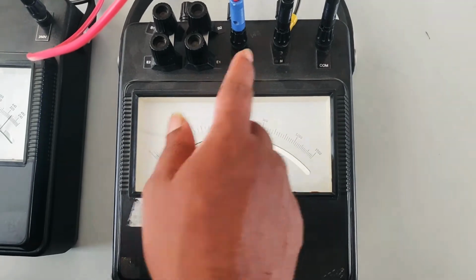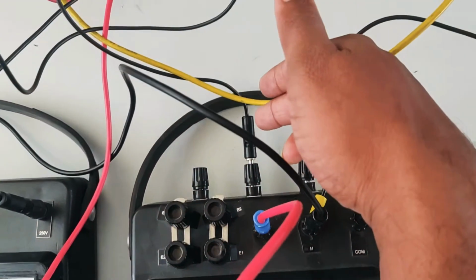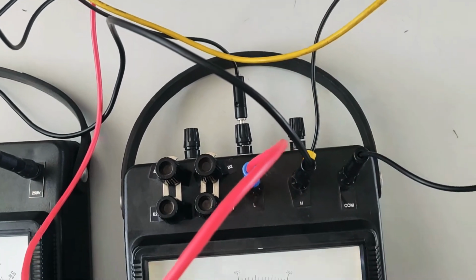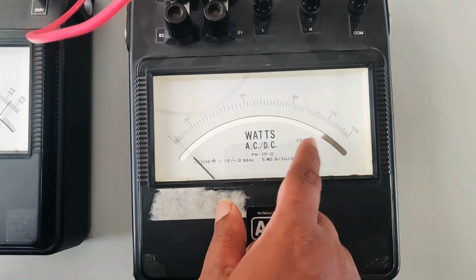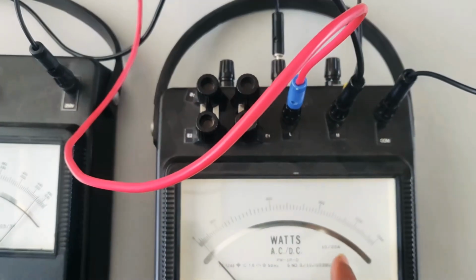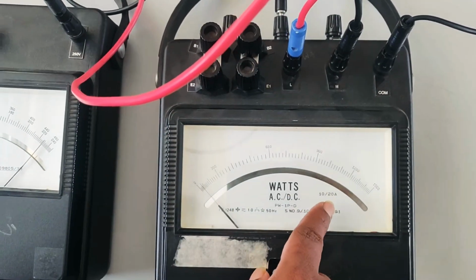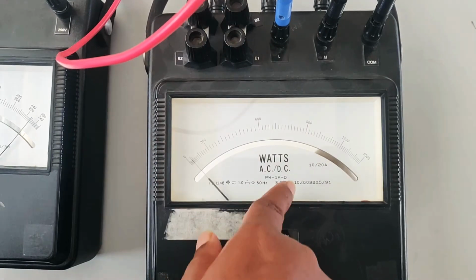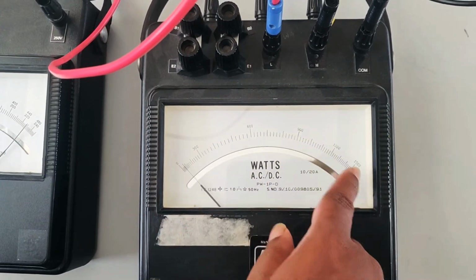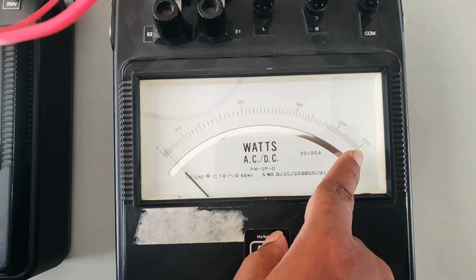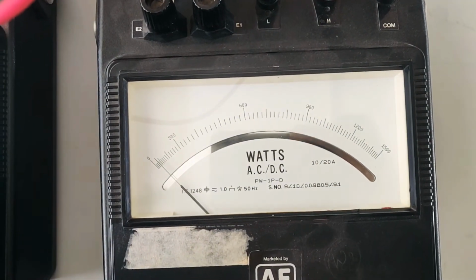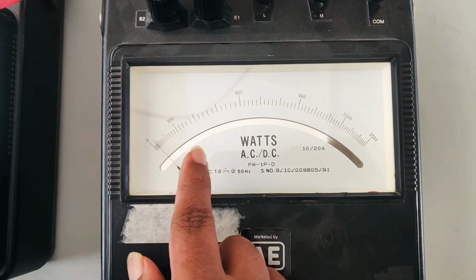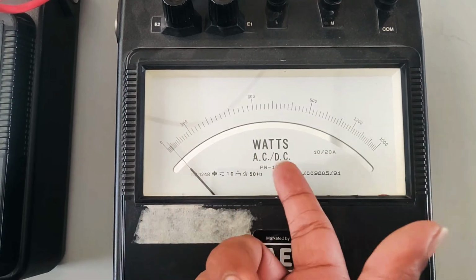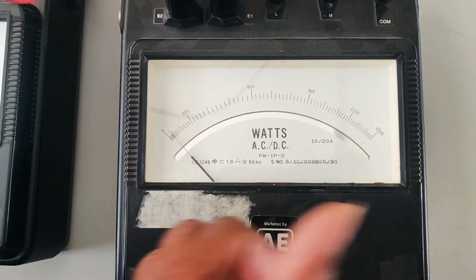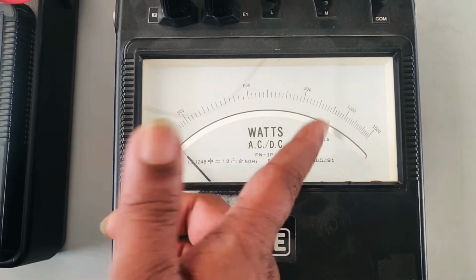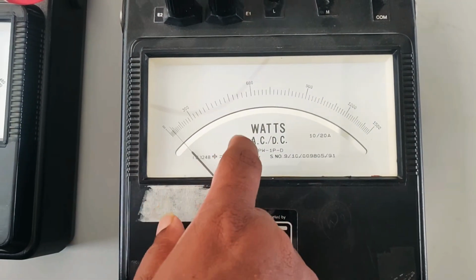So V is the voltage setting. What you have done, you have selected the voltage setting as 300. I is the current setting. Okay, you have an option between 10 and 20. Since the coils are in parallel, it is set for 20. So 300 into 20, and then it is a unity power factor meter. So 300 into 20 divided by FSR. What is the FSR here? Full scale reading 1500. So 300 into 20 divided by 1500 will be the wattmeter constant. 300 into 20 means 6000. 6000 divided by 1500, that is 4, will be the wattmeter constant. So 80 into 4 will be the no load losses of the induction motor.